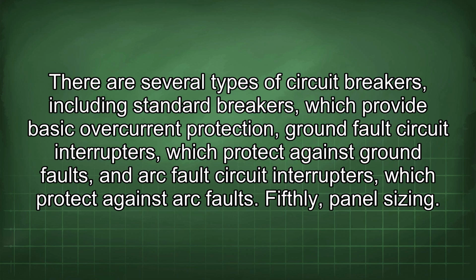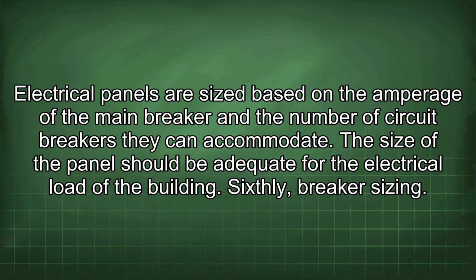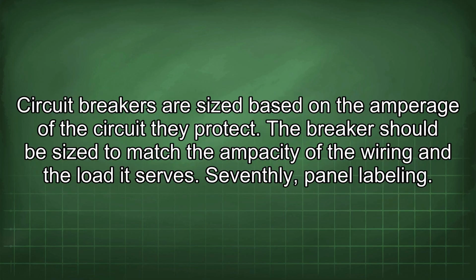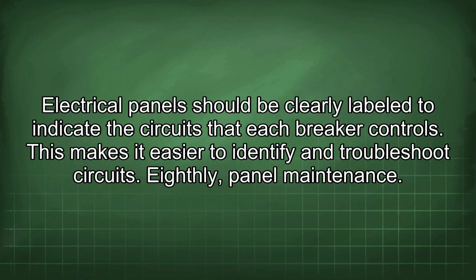Fifthly, panel sizing. Electrical panels are sized based on the amperage of the main breaker and the number of circuit breakers they can accommodate. The size of the panel should be adequate for the electrical load of the building. Sixthly, breaker sizing. Circuit breakers are sized based on the amperage of the circuit they protect. The breaker should be sized to match the ampacity of the wiring and the load it serves. Seventhly, panel labeling. Electrical panels should be clearly labeled to indicate the circuits that each breaker controls. This makes it easier to identify and troubleshoot circuits.